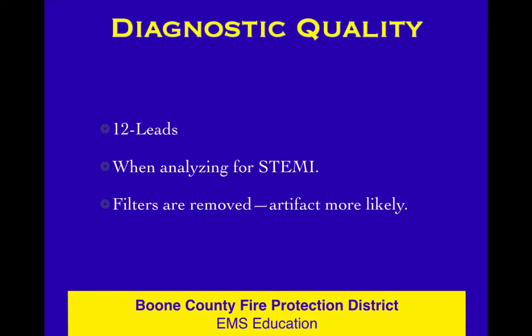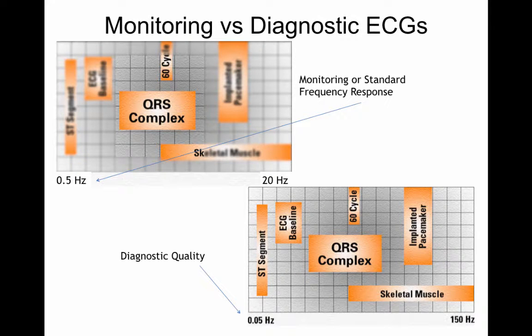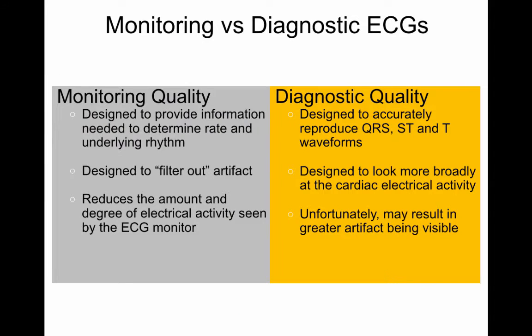Diagnostic quality takes off all the filters — however, that means more artifacts are going to get through. Here's an interesting diagram: in monitoring quality you can see the QRS, but the rest is filtered out. In diagnostic quality, all the various interferences are now seen — you see all the junk, but you can make fine analysis of the ST segment. There's also a very good side-by-side summary of monitoring and diagnostic quality. Diagnostic is what we're looking for: you get a little more artifact, but it lets you look at ST segment changes, and that's what you get with the 12-lead.